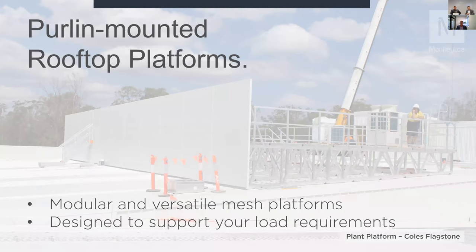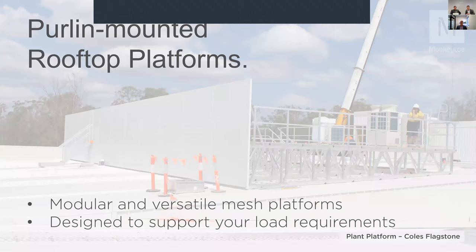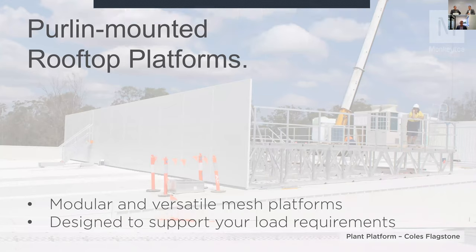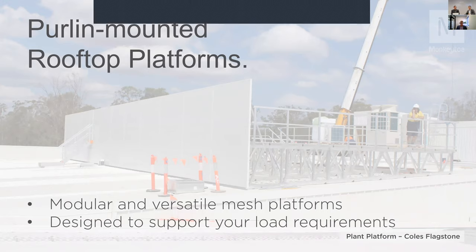Purlin-mounted platforms are also a modular system, which means they're really versatile and flexible. They're designed to suit your load — whether that's a standard rating of 2.5 kPa right up to 5 kPa for some of your larger chiller units. That example shown is at another Coles project — Coles Flagstone — which was a purlin-mounted platform design.